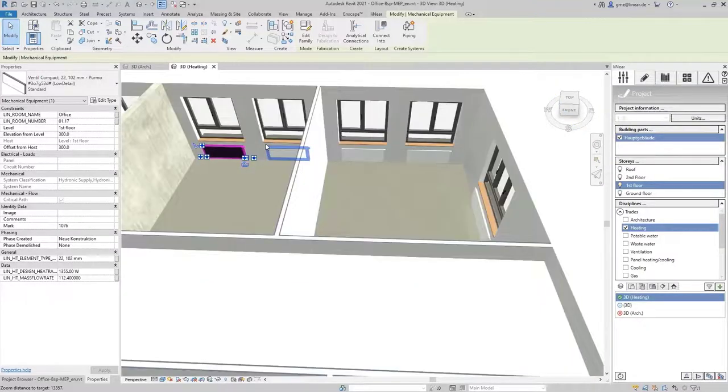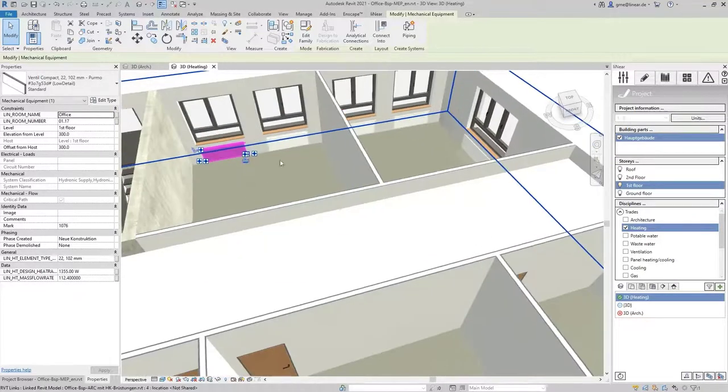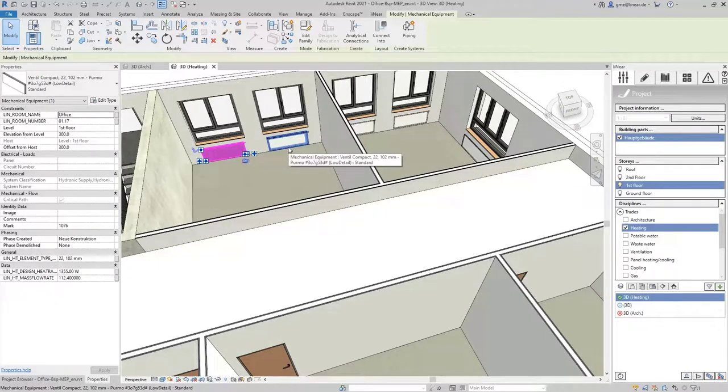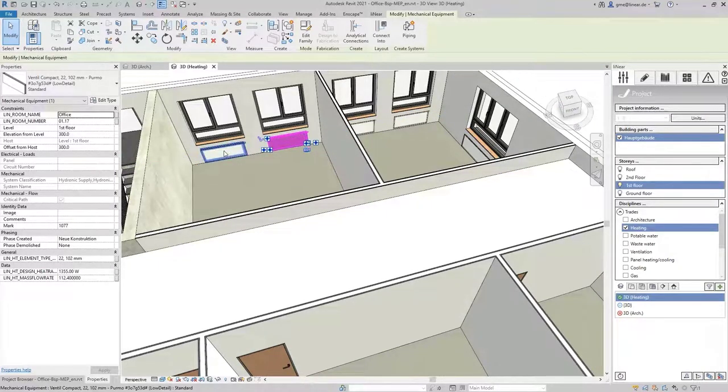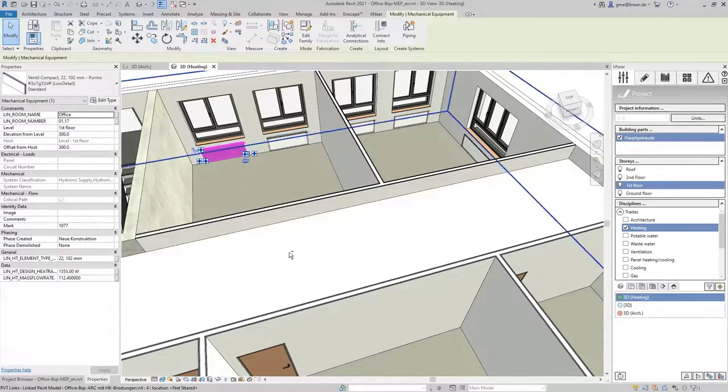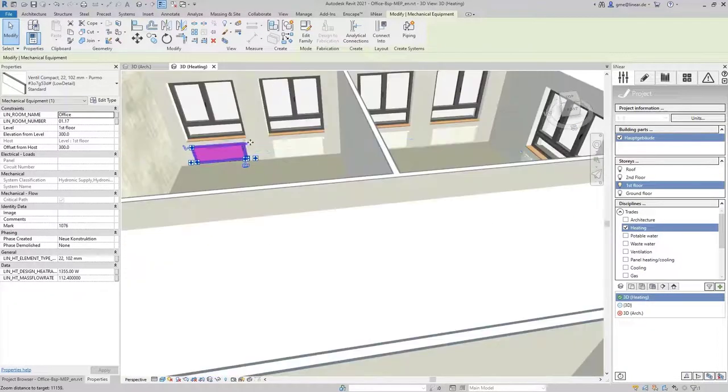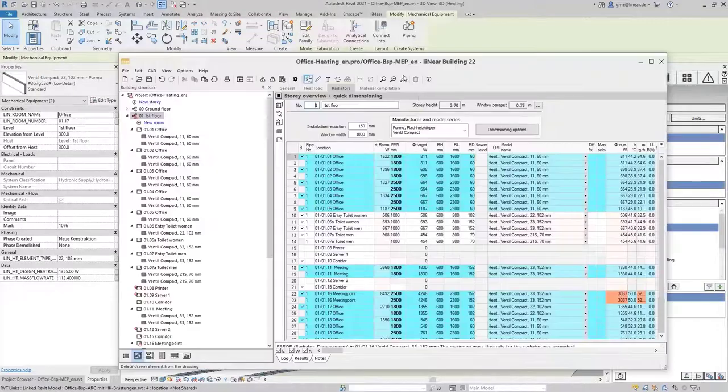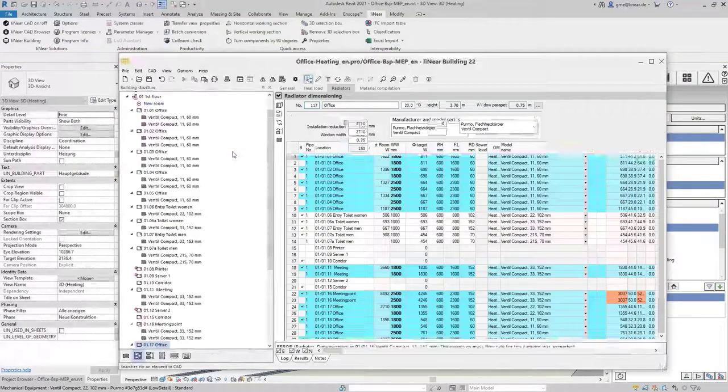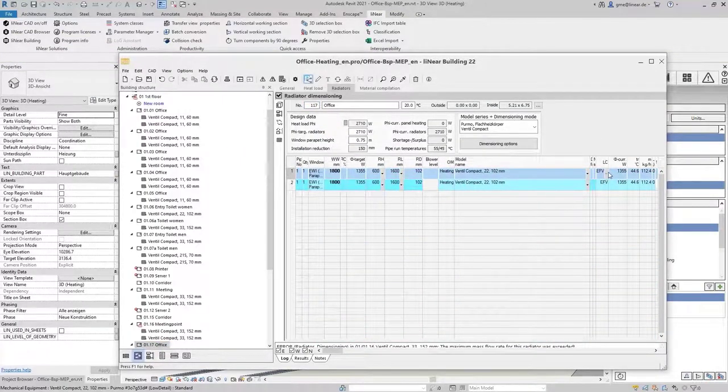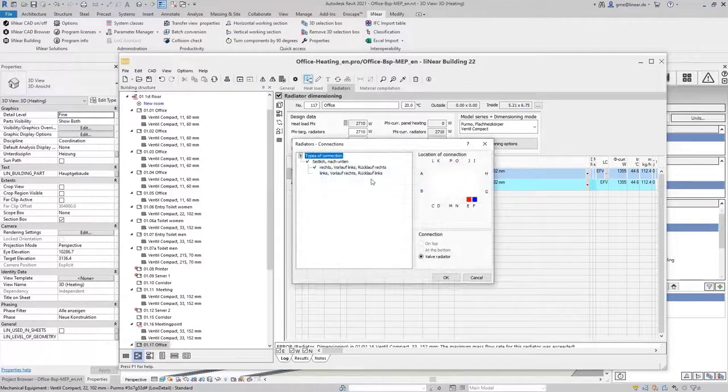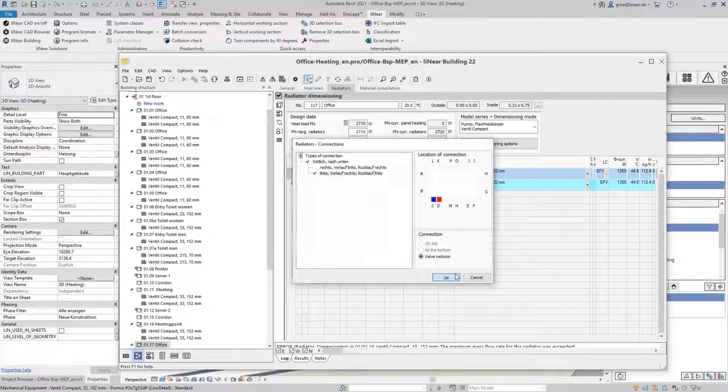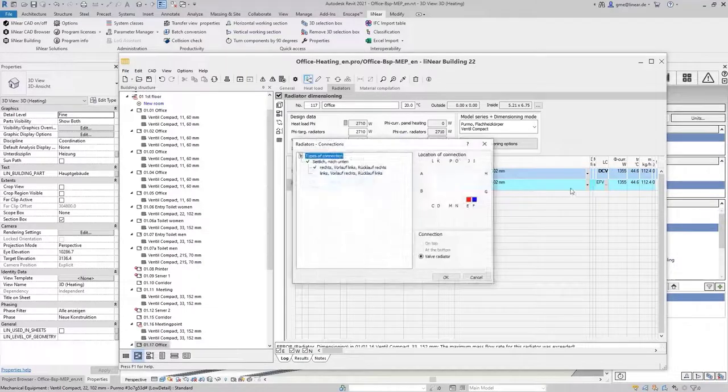Through the direct connection of Revit and linear building you also have the possibility to make changes very easily. For example we can change the connection position of these two radiators. Using the pipette tool in linear building I can easily navigate to these components and change the connection position. Here I change the position from right to left and can then transfer these changes to the model using the refresh function.